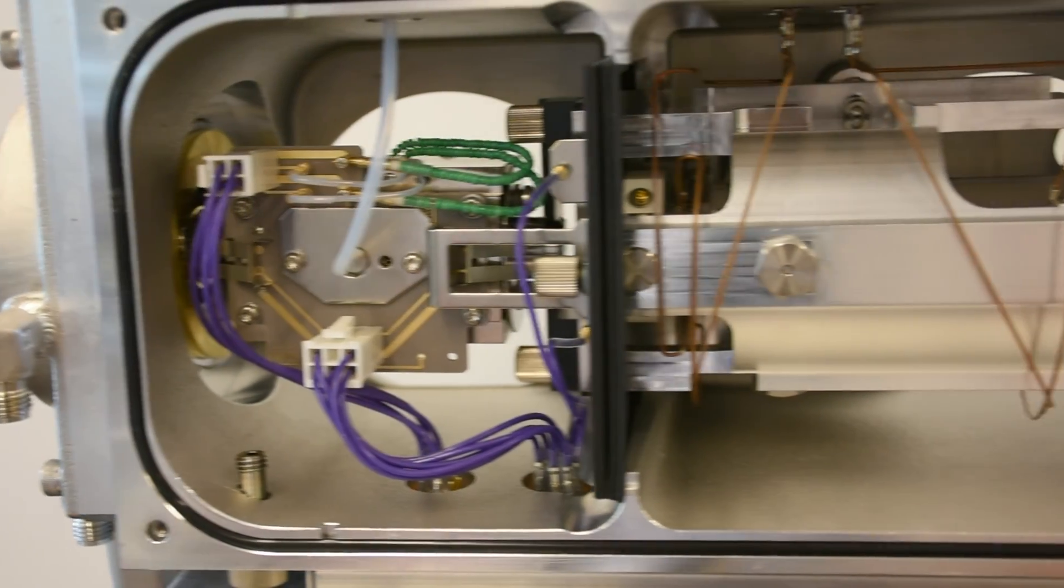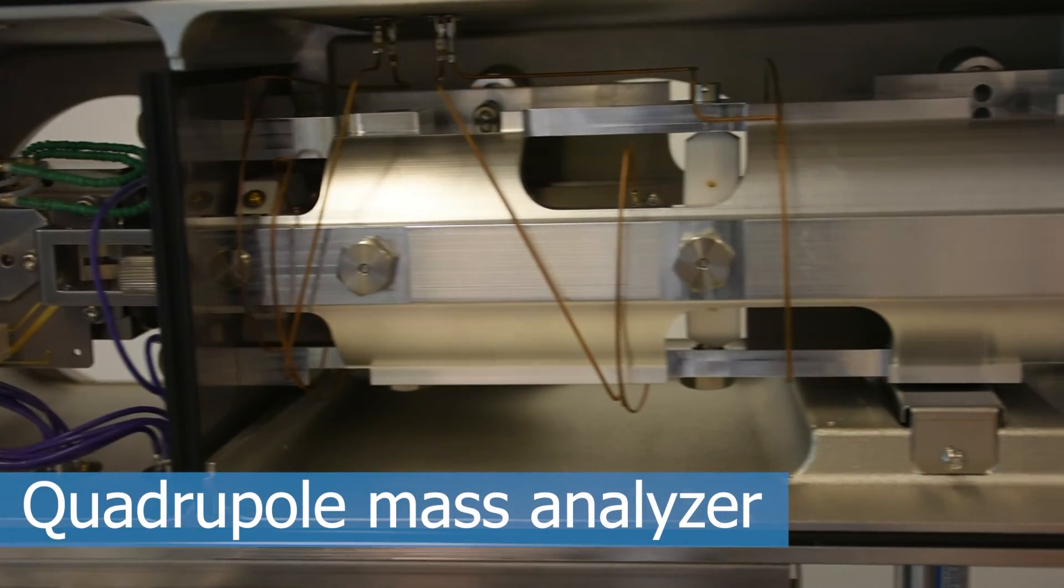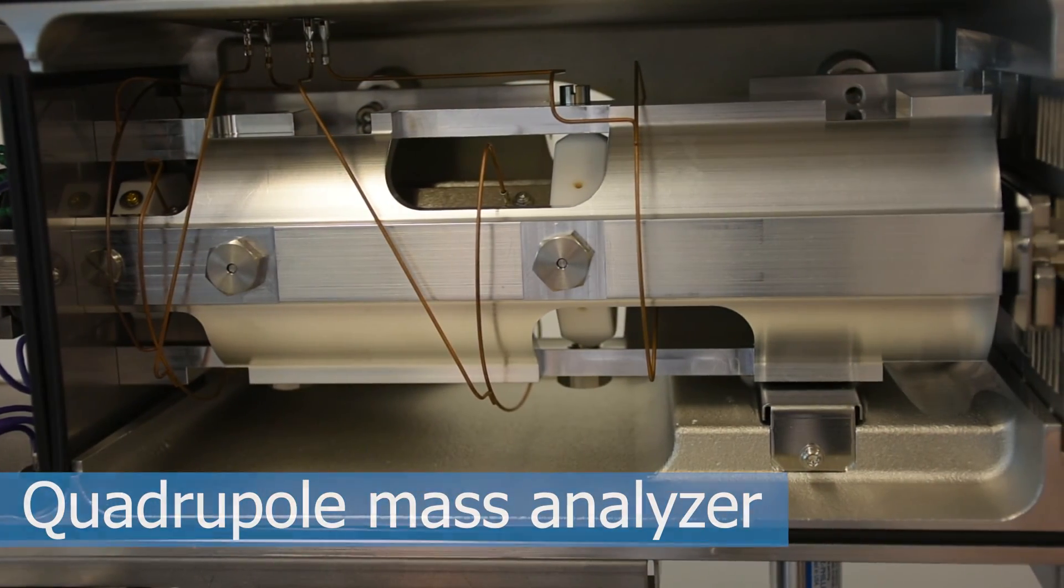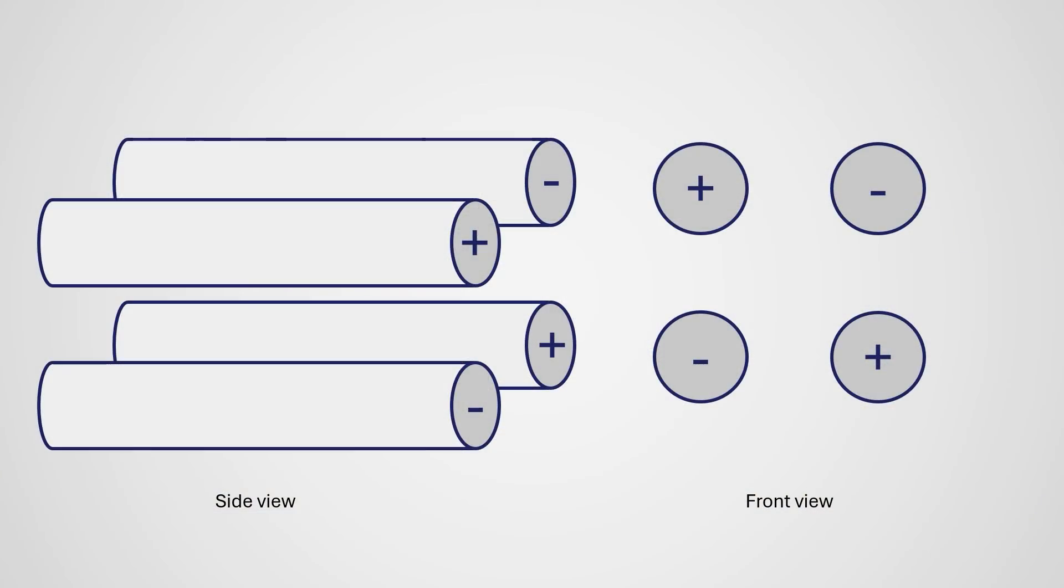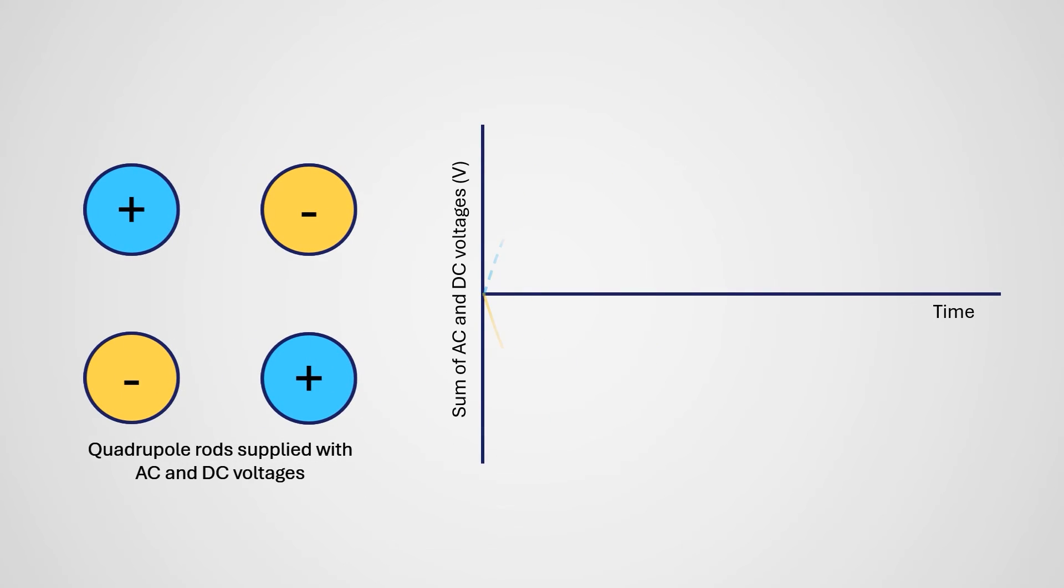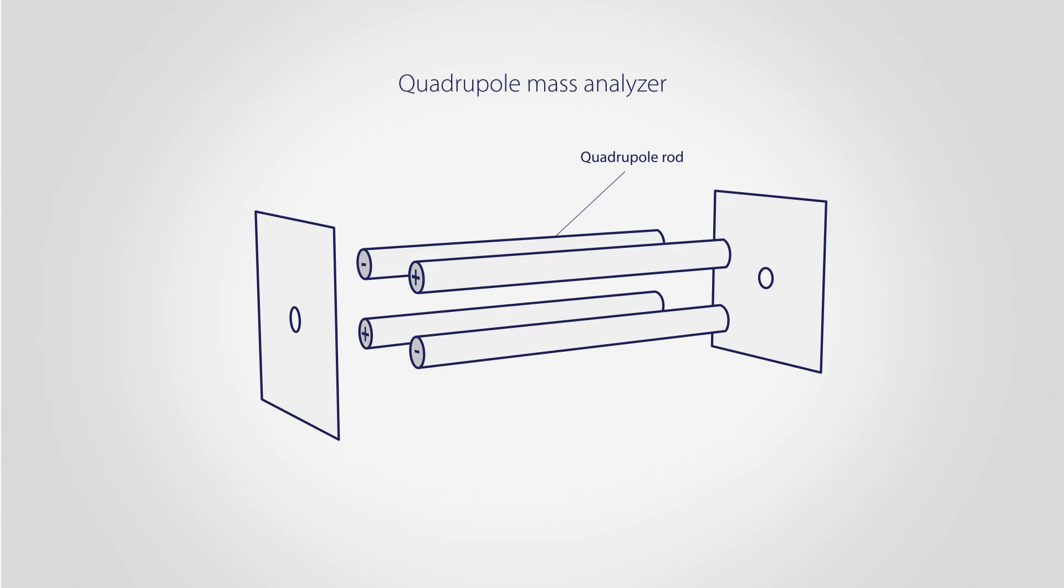The ions proceed to the quadrupole mass analyzer. It filters ions by their mass to charge ratio. The quadrupole consists of four parallel rods, each with both AC and DC voltages on them. The details get complicated, but basically pairs of rods have opposing polarity, and that positive negative polarity switches back and forth rapidly. All of that generates an oscillating electric field down the center line of the quadrupole.